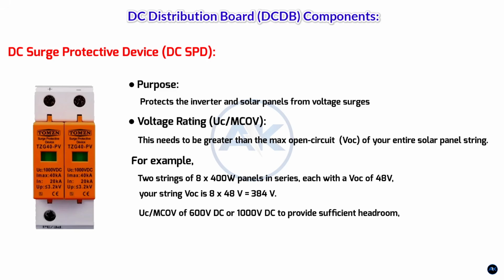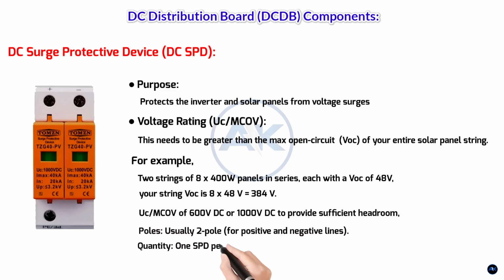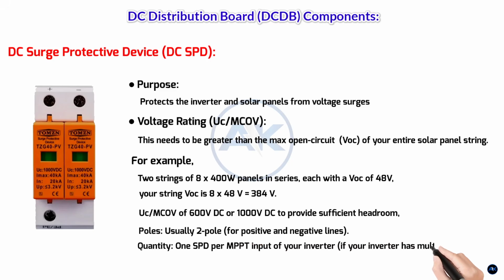Nominal discharge current is typically 20 kiloamperes for residential systems. Maximum discharge current, IMAX, often 40 kiloamperes. Type: usually type 2 for typical residential PV installations. Some systems may also incorporate a type 1 SPD at the point of entry for direct lightning protection. Poles: usually 2-pole for positive and negative lines. Quantity: 1 SPD per MPPT input of your inverter if your inverter has multiple MPPTs. Or, if using a combiner box for multiple strings, 1 SPD for the combined output.